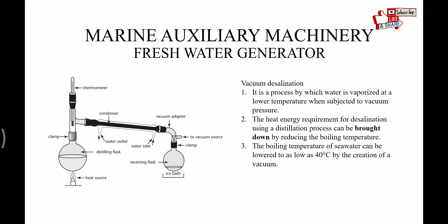The basic principle on which the freshwater generator works on board ship: there are two principles — one is vacuum desalination and the other is reverse osmosis. In the vacuum desalination process, water is vaporized at lower temperature when subjected to vacuum pressure. The heat energy required for desalination using a distillation process can be brought down by reducing the boiling temperature. The boiling temperature of sea water can be lowered as low as 40 degrees by creation of vacuum. As we reduce pressure, the boiling point of water decreases, consuming very less energy, and this can be used to produce water on board ship. The energy from jacket cooling water is used on board ship for this purpose.